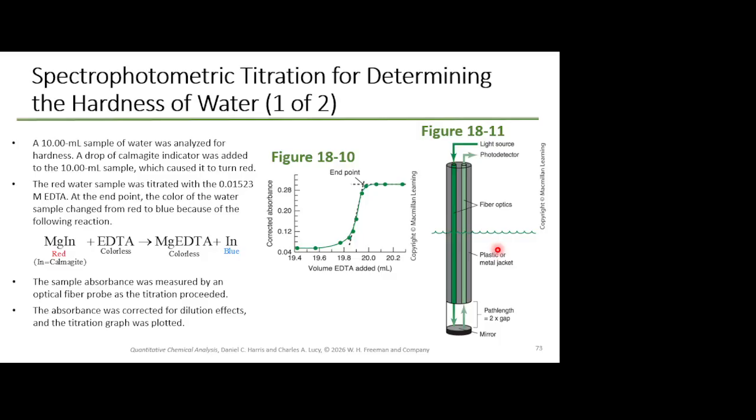But you need to make sure it mixes well and that your mixing is not going to interfere with your spectrometer. Sometimes you have to get a little more complex, where you pass the sample around and circulate it into your spectrometer. But most of these systems can be as simple as a container you put light through, or a little probe that looks a lot like a pH meter, just with fiber optics connecting the ends that pass light.